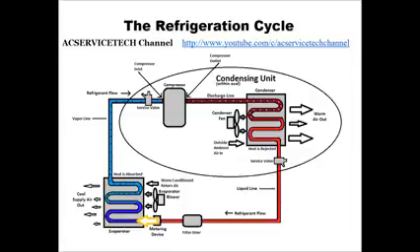The refrigerant is actually absorbing heat once it enters the evaporator coil. As it absorbs enough heat, it turns into that saturated state in the middle of the evaporator coil, where most of the energy absorption is taking place. Right after that is where it turns into a low pressure, low temperature vapor, until it comes out of the evaporator coil, and it's still absorbing heat.